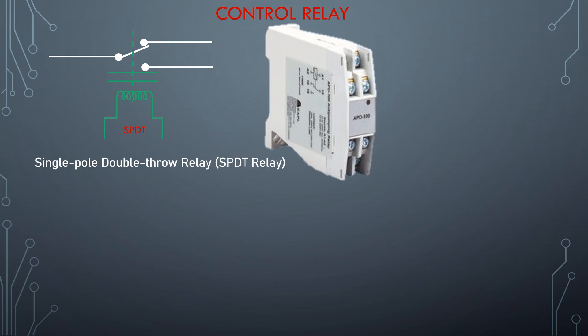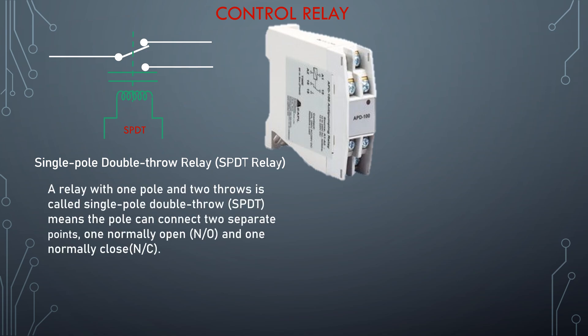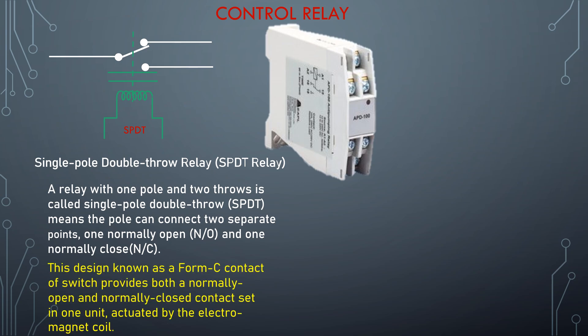Now, single pole double throw relay — SPDT relay. A relay with one pole and two throws is called single pole double throw, SPDT. It means the pole can connect to two separate points: one normally open (NO) and one normally closed (NC). This design, known as a Form C contact switch, provides both a normally open and normally closed contact set in one unit actuated by the single electromagnet coil.